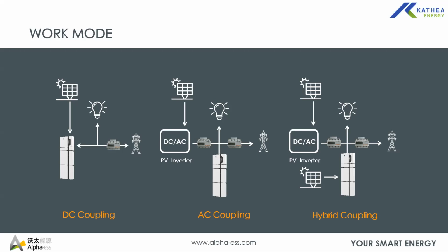However, you would need a second meter, which has to be installed at the output of the PV inverter. This meter is there to measure the output of the PV inverter, and at the same time make sure that the Alpha system does not feed back to your PV inverter, to avoid damaging it. So that meter is essential to prevent feeding back to the PV inverter, and also to calculate the output of the inverter. So now on the system you have two meters. These meters are daisy chained together on an RJ45 to the inverter.